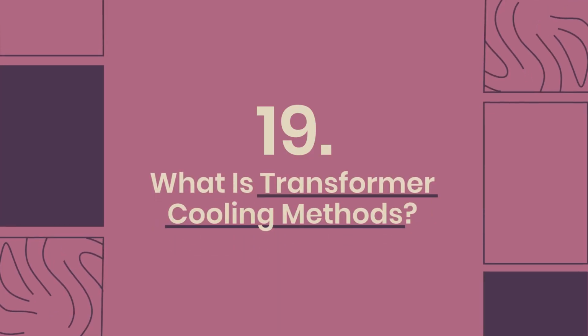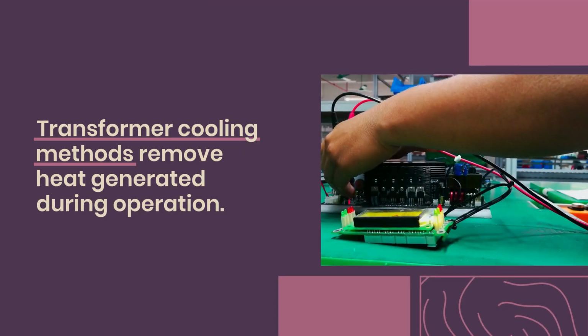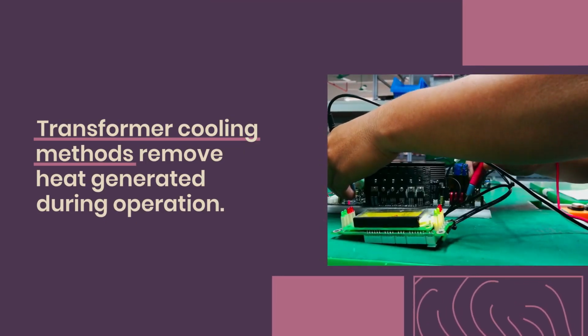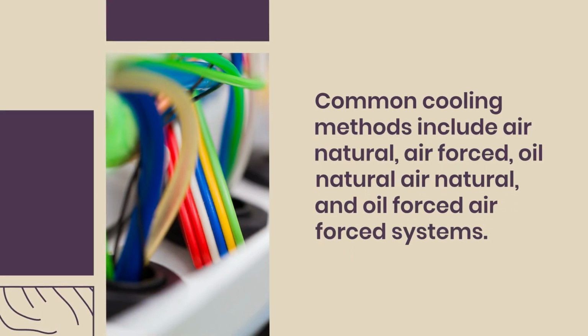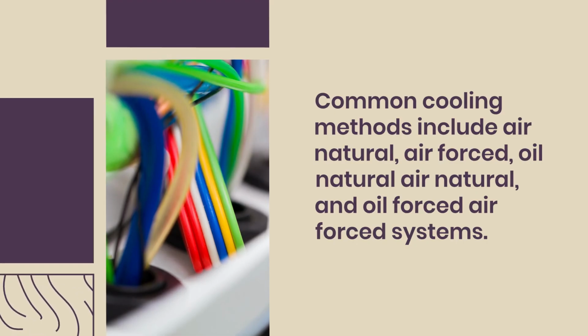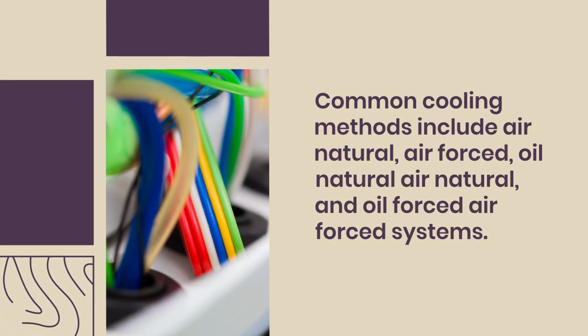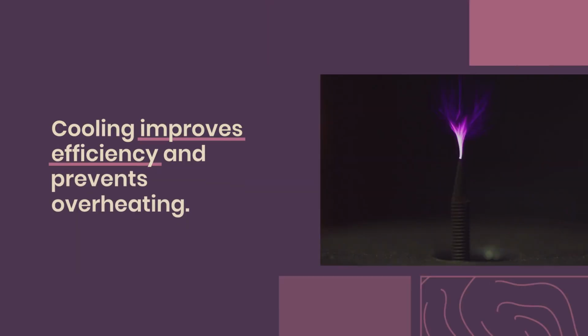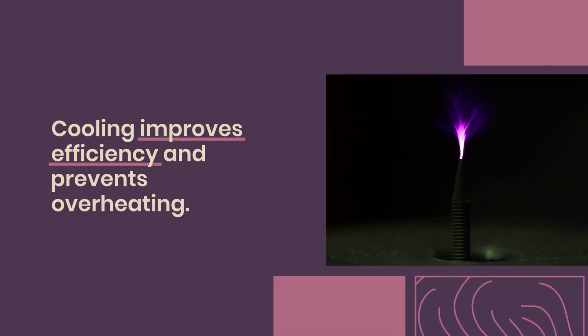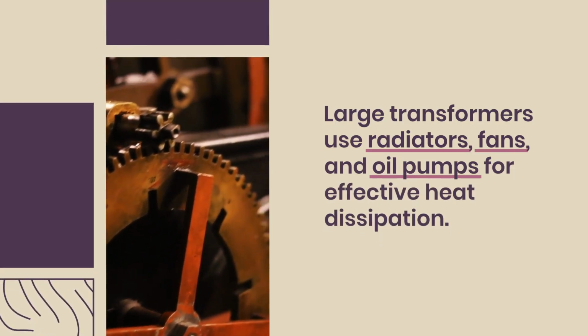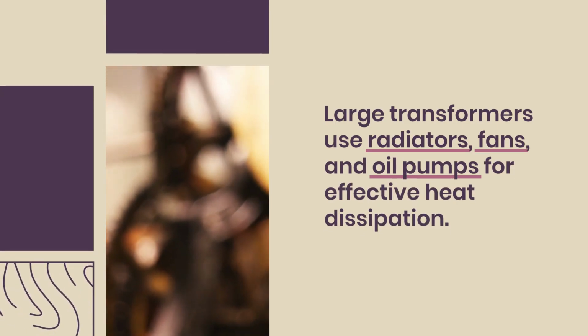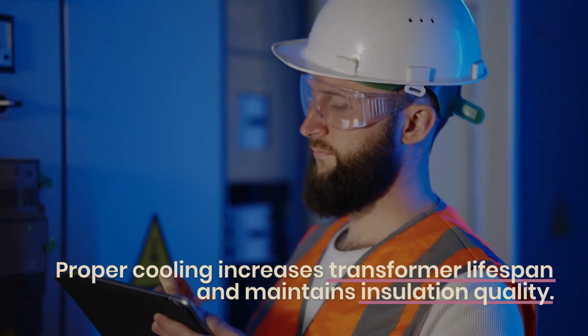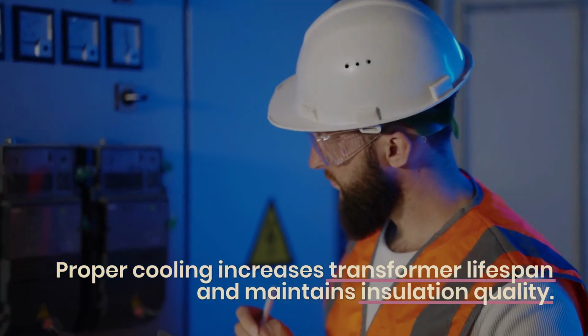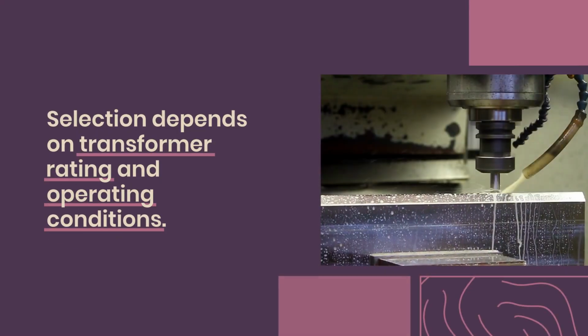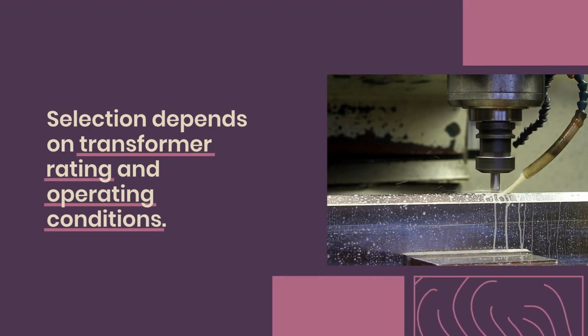19. What is transformer cooling methods? Transformer cooling methods remove heat generated during operation. Common cooling methods include air-natural, air-forced, oil-natural air-natural, and oil-forced air-forced systems. Cooling improves efficiency and prevents overheating. Large transformers use radiators, fans, and oil pumps for effective heat dissipation. Proper cooling increases transformer lifespan and maintains insulation quality. Selection depends on transformer rating and operating conditions.